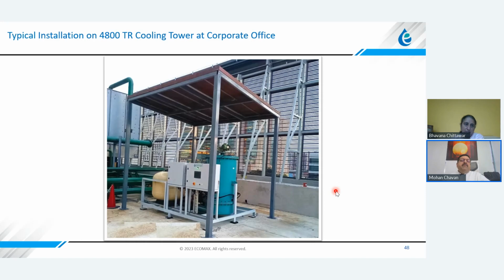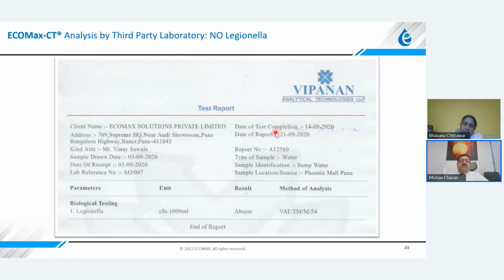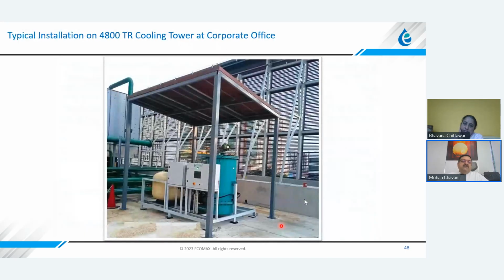And this also has an impact on the energy efficiency improvement of the chillers, because as we improve the delta T in the cooling tower, your energy consumption by the chillers in the buildings will also improve. This one is one of the installations at an IT office, wherein this system is installed, and they got substantial reduction in the blowdown water consumption. So I will cover this as another case study, after this presentation.